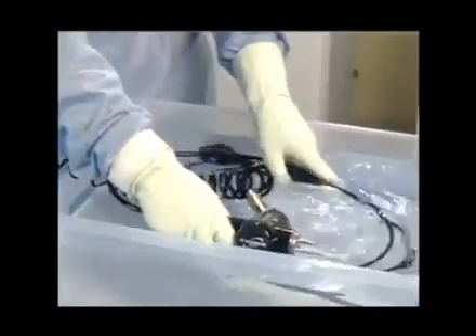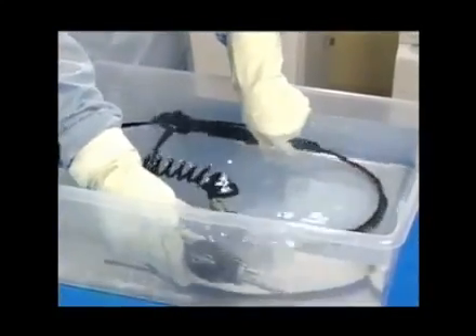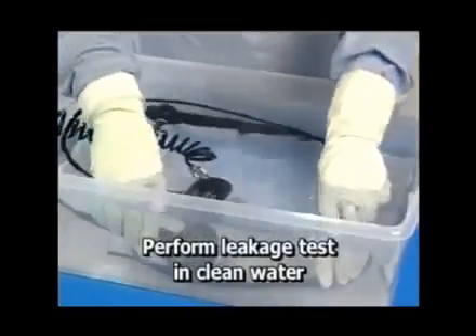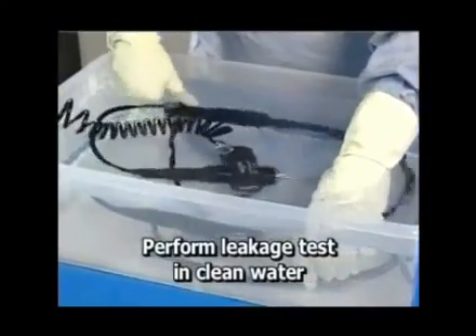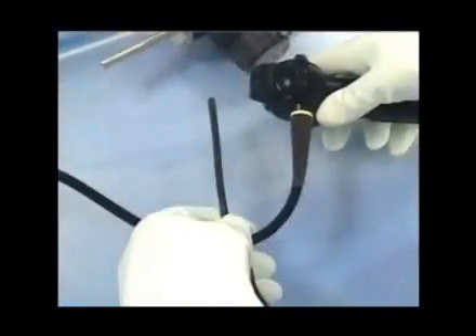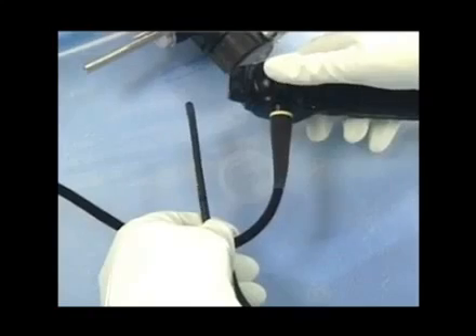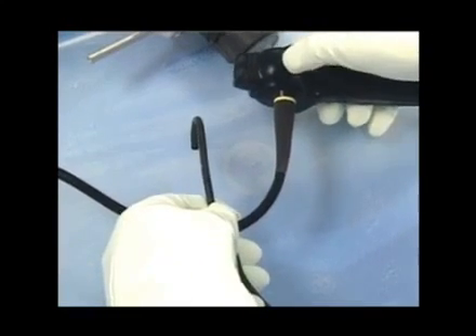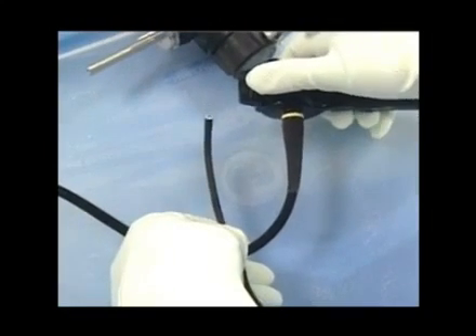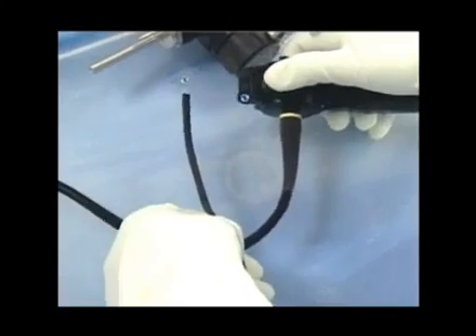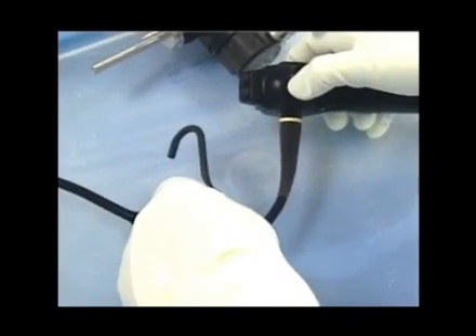Now immerse the bronchoscope in clean water. Do not leak test in detergent, as detergent will hinder visualization of leaks. Angulate the bronchoscope tip in both directions. Deflecting the tip will help expose any pinholes that may exist in the bending section rubber.